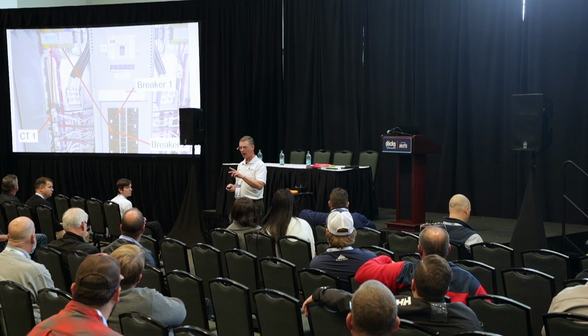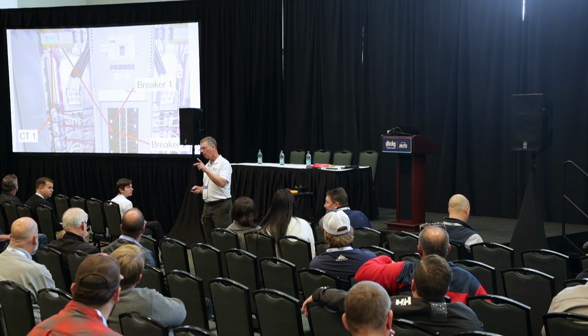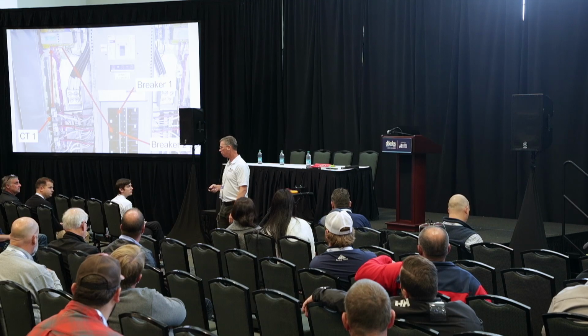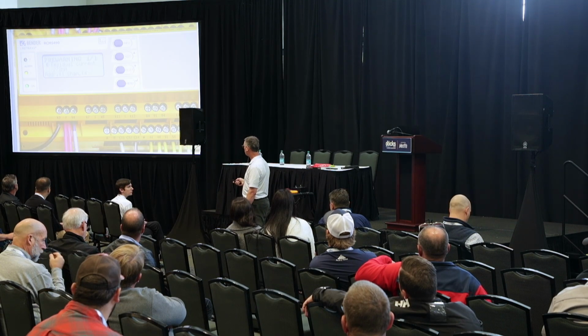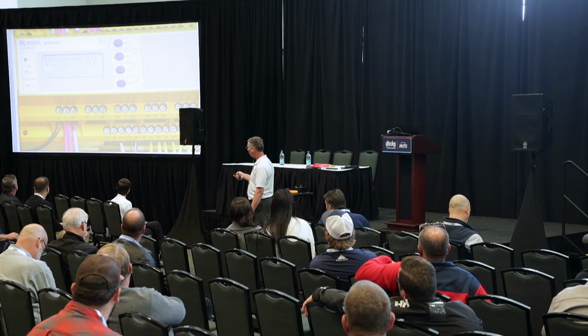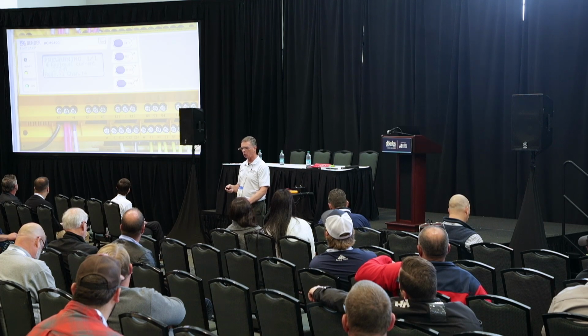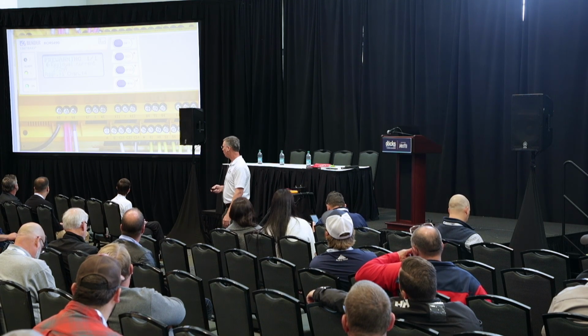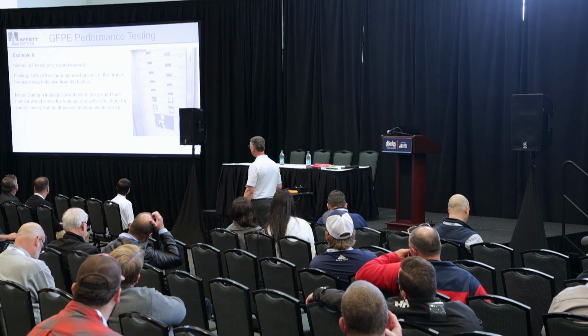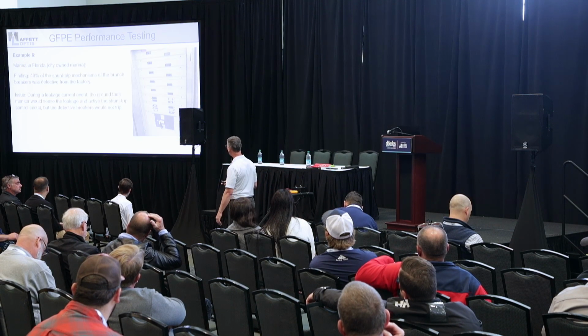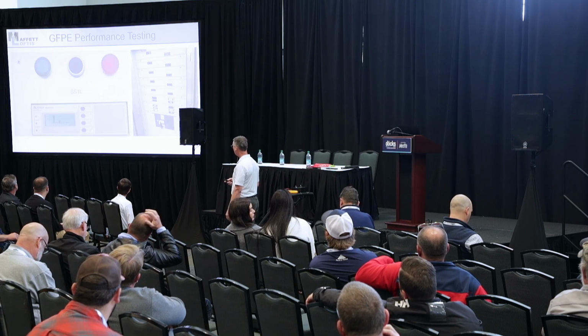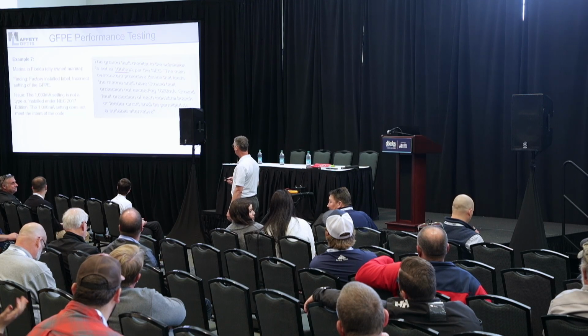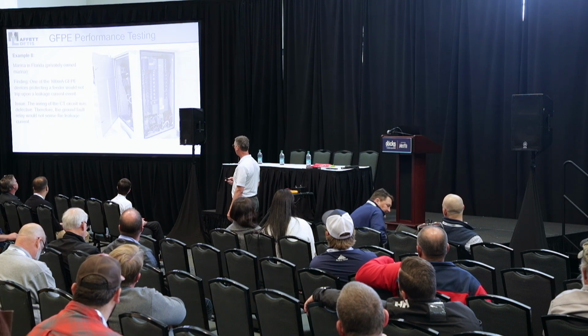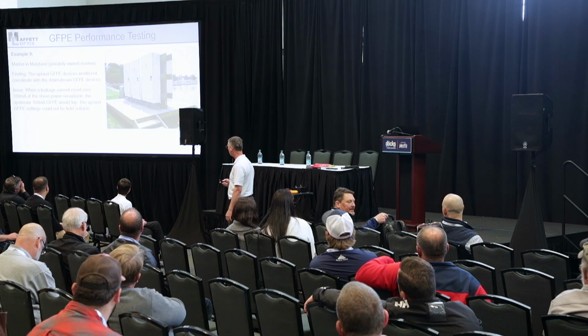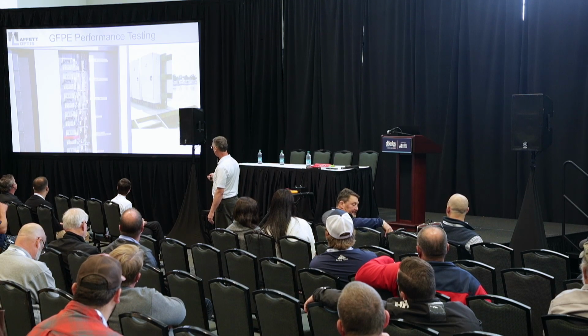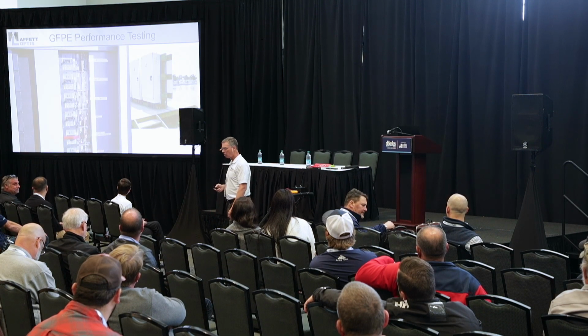And sometimes it's manufacturing issues, and sometimes it can be contractor issues. And I found both. And you can see how much leakage current I was leaking, even at 272 milliamps, and it would never trip. So I find stuff like that all the time. There's all kinds of, here's 40% of the breakers didn't work. That's not an issue, that's not a good deal. Here's another one that GFP circuit wouldn't work. All kinds of, this was an issue that they disabled the GFPE.